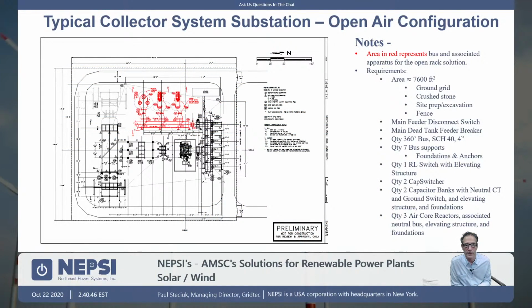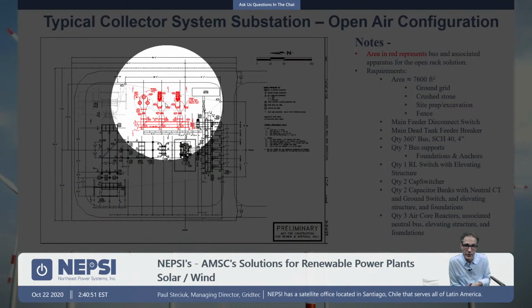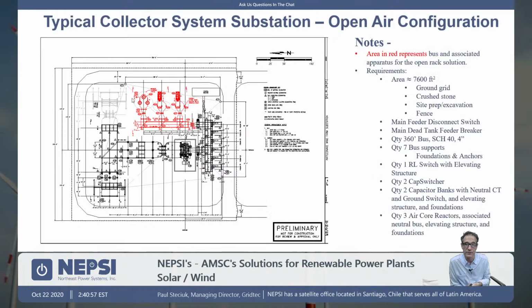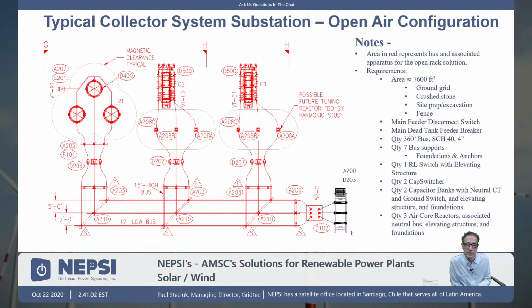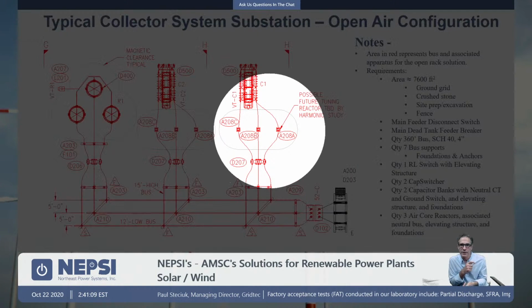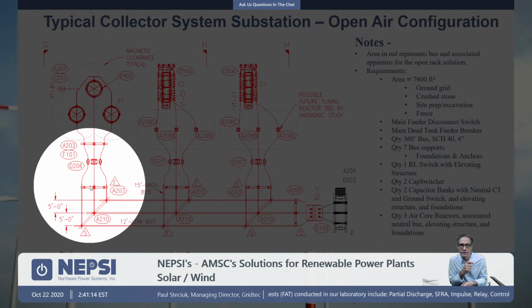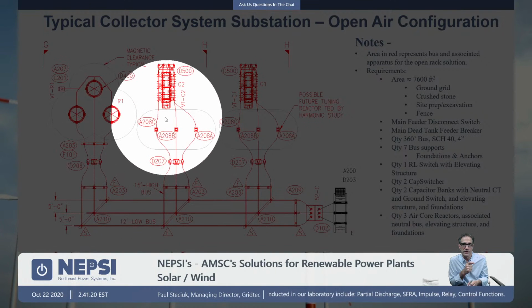And if we were to look at it from a layout standpoint, the area in red here represents that shunt reactive system. So remember, shunt reactor bank plus capacitors. And NEI did a really good job here because they did make this a filter-ready system. You can see here on the left, we've got shunt reactors. There's the switching device, some stands for bus bars. We've got bus bars here, switching device, and there's a space here for reactors.